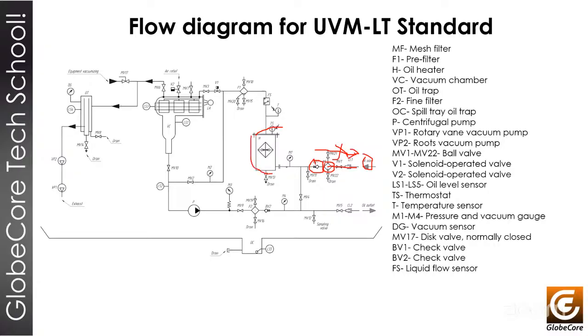And then we have here the heater. This heater will increase the temperature of the oil, as needed for the dehydration and degassing. Then we have the flow sensor. This is needed for the activation of the heater. If this flow sensor doesn't detect oil flow in this way, the heater will not work, because we don't want the heater to start working if there is no flow of oil inside of it. That means only if the flow sensor detects flow of the oil in this heater, the resistor will turn on.